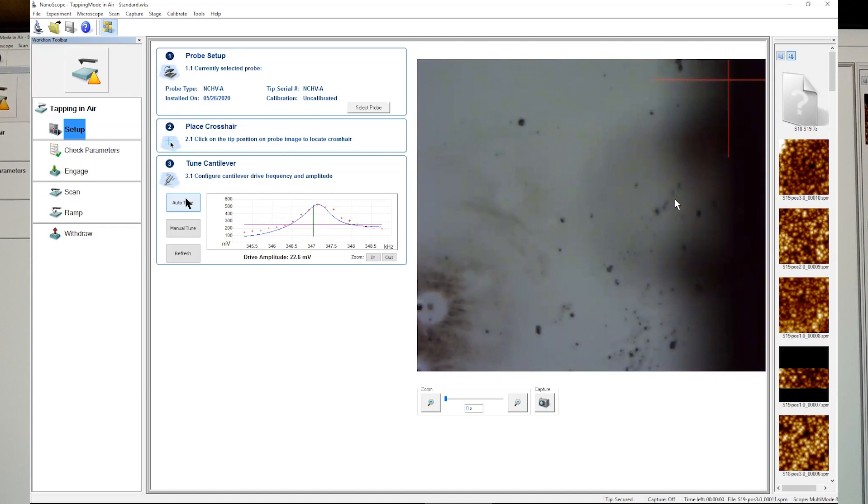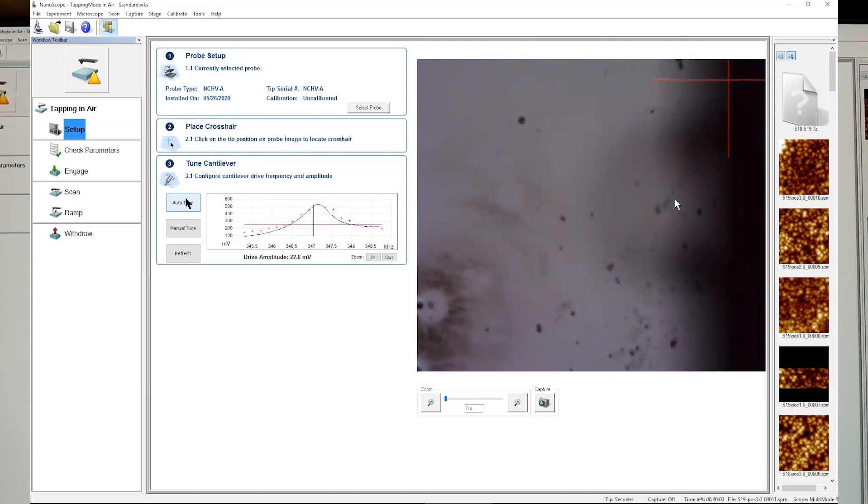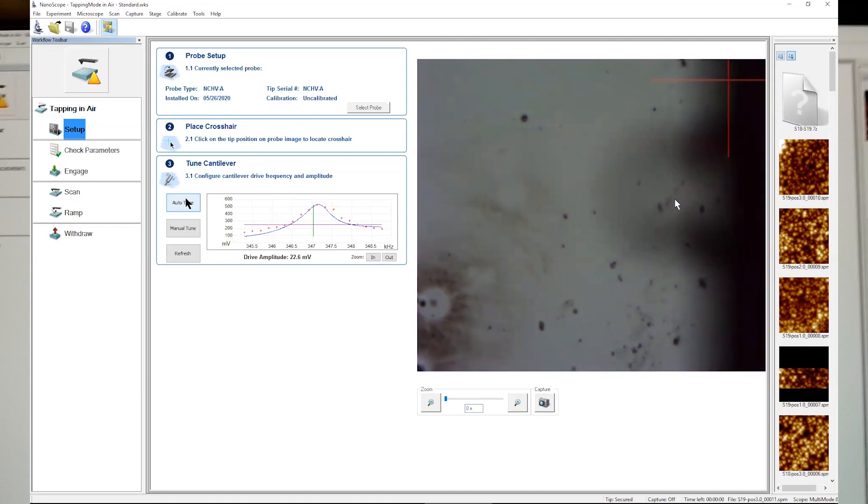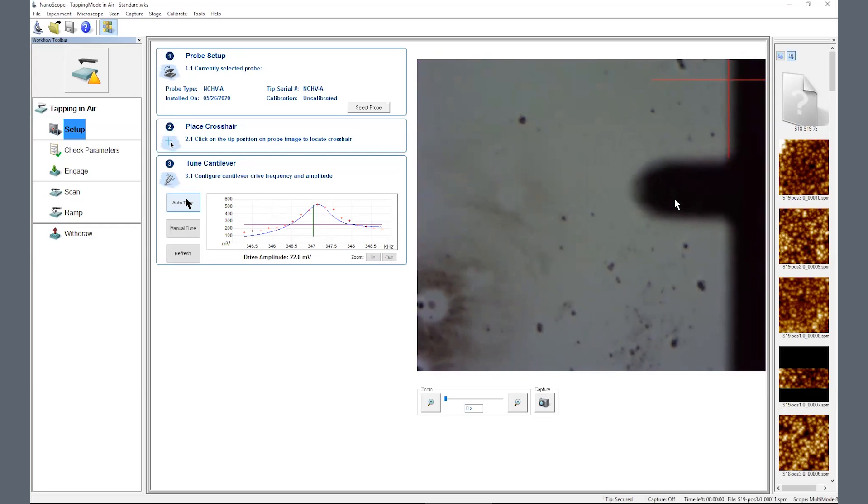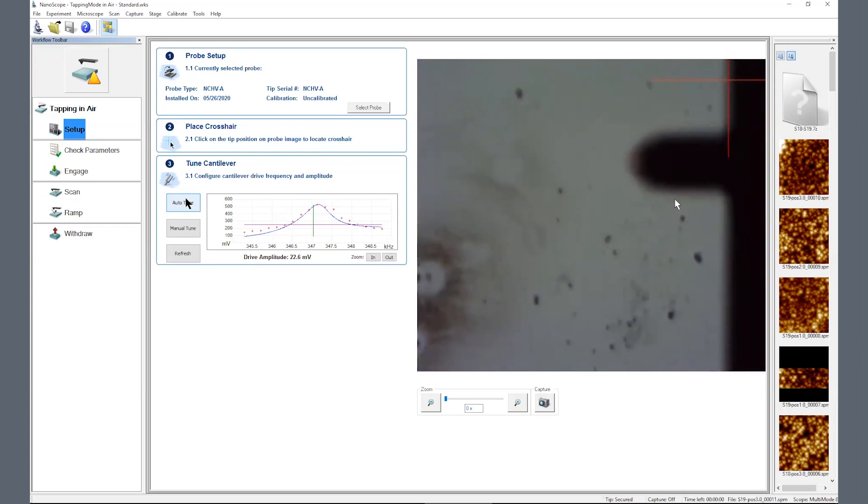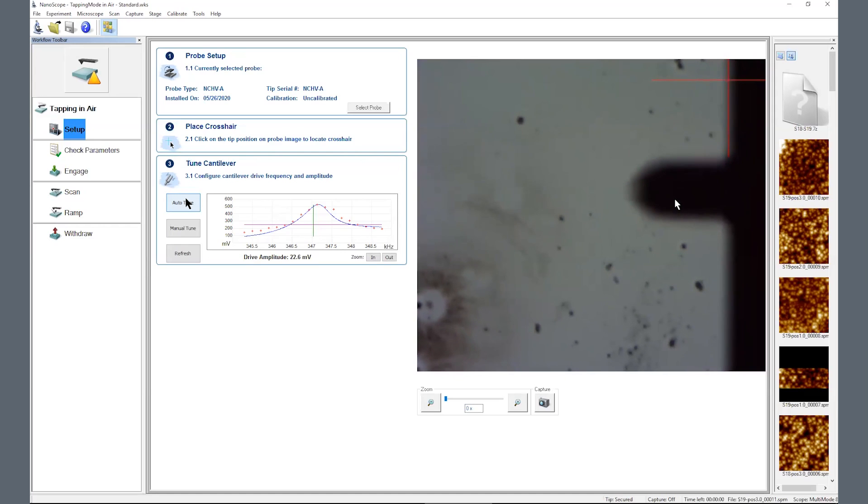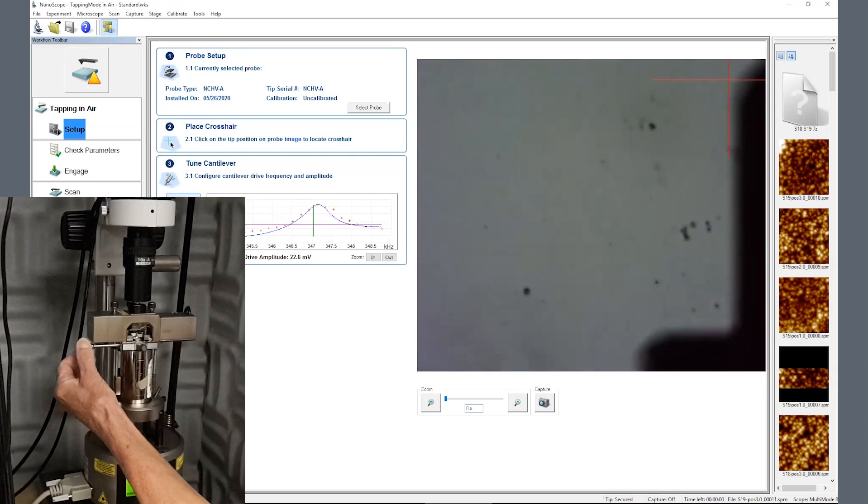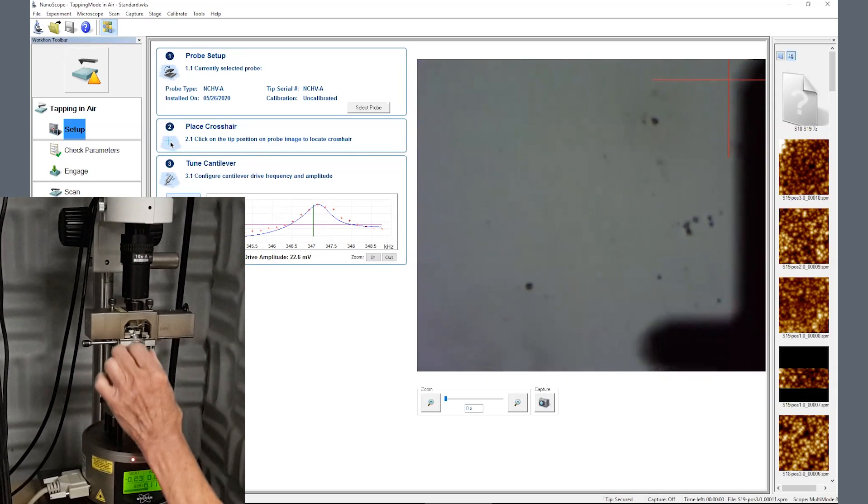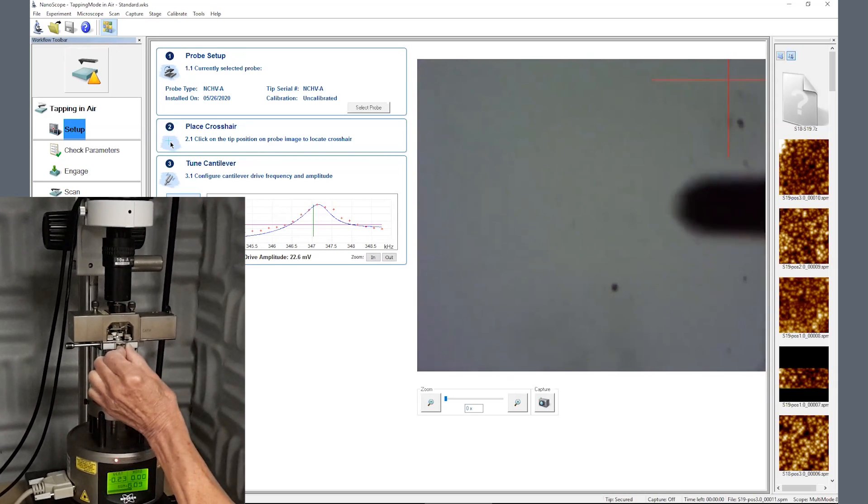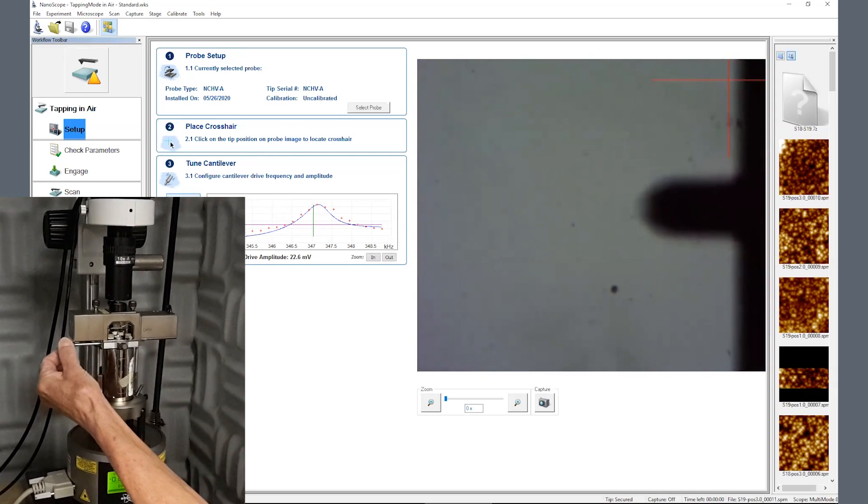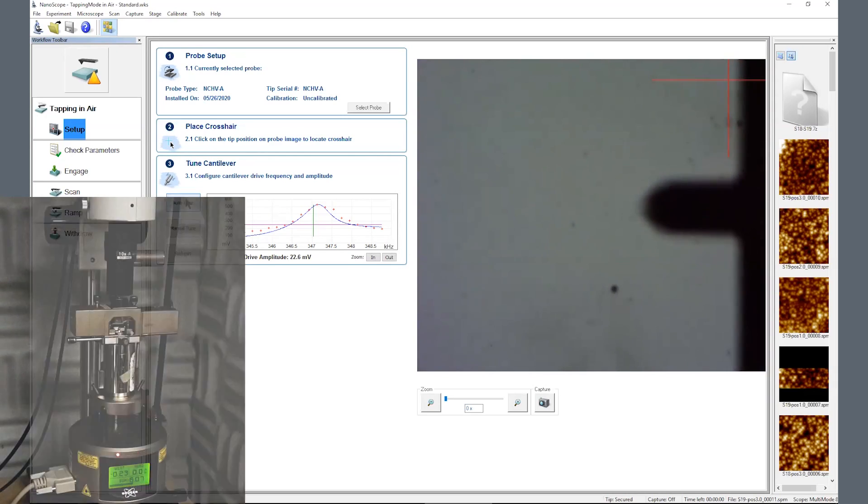Adjust the illumination intensity as needed. Slowly lower the optical head to bring the probe closer to the sample surface using the down position on the microscope base. Allow some defocus to prevent the tip from coming into contact with the surface. Reposition the probe using the XY knobs below the optical head to a clean area of interest for imaging.